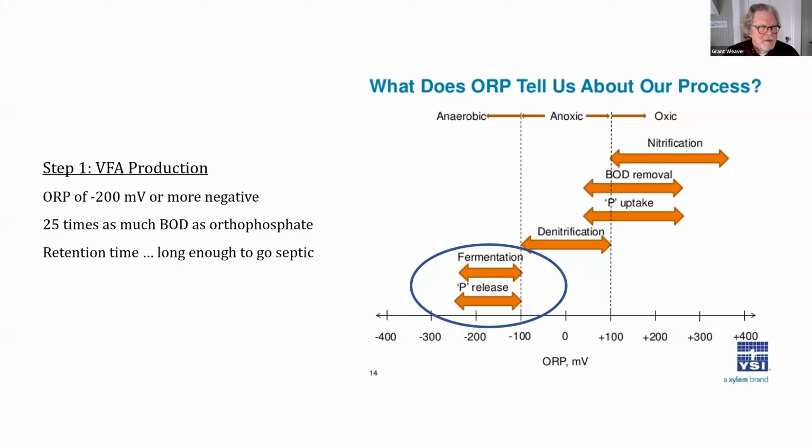So we need an environment that's just like a septic tank, something short of anaerobic digestion. If you're fully anaerobically digesting, these little VFAs, they're the acids in the acid alkalinity ratio, they're a sour digester. If you have an anaerobic digester, you want none of these. You're converting them to methane gas. So we want a sour digester, kind of fixed on the word septic now. I think people can relate to that.